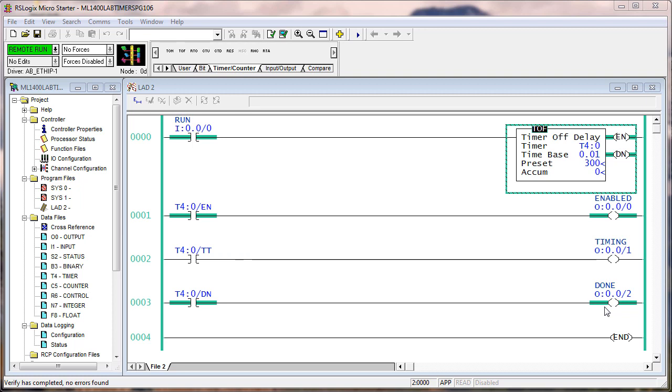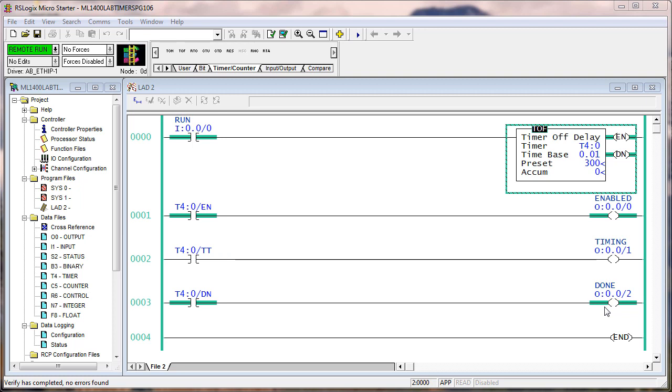In the second column there, number one run, zero goes false. The second thing that happens is the enable bit is cleared, the timer timing bit is set, and the accumulator starts incrementing. And then after a period of time based on the preset, when the accumulate equals the preset, that would be number three. And then number four, the done bit is cleared, and the timer timing bit is cleared.